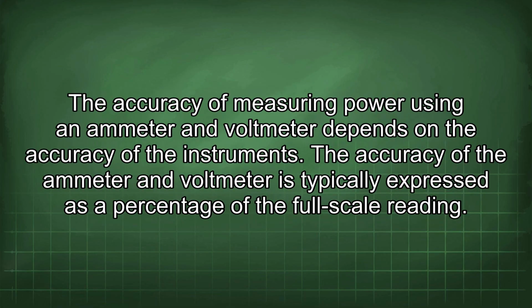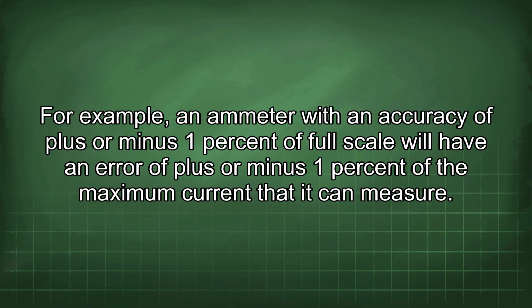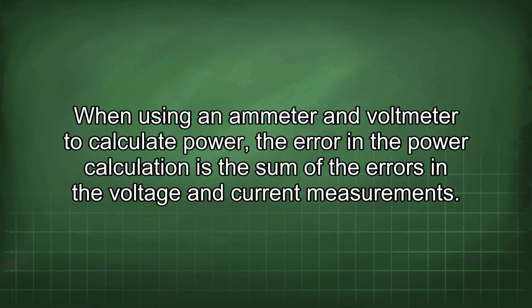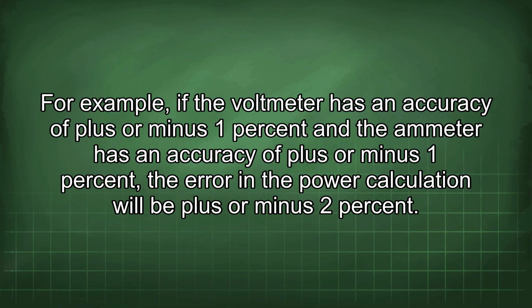The accuracy of measuring power using an ammeter and voltmeter depends on the accuracy of the instrument. The accuracy of the ammeter and voltmeter is typically expressed as a percentage of the full-scale reading. For example, an ammeter with an accuracy of plus or minus 1% of full scale will have an error of plus or minus 1% of the maximum current that it can measure. When using an ammeter and voltmeter to calculate power, the error in the power calculation is the sum of the errors in the voltage and current measurements. For example, if the voltmeter has an accuracy of plus or minus 1% and the ammeter has an accuracy of plus or minus 1%, the error in the power calculation will be plus or minus 2%.